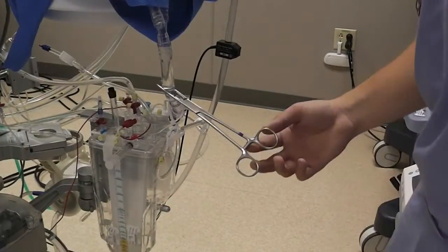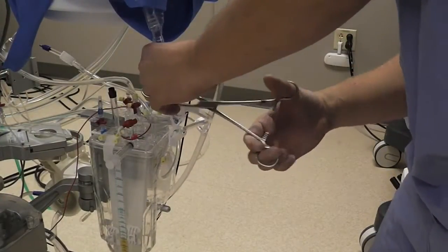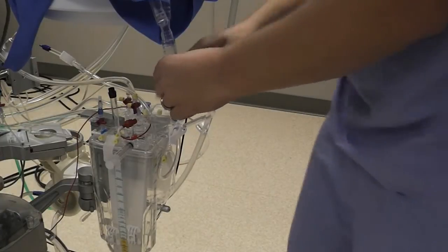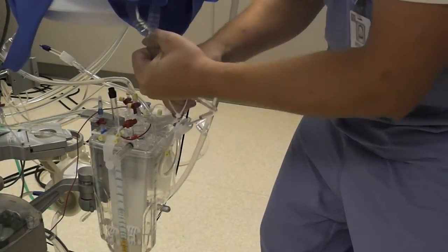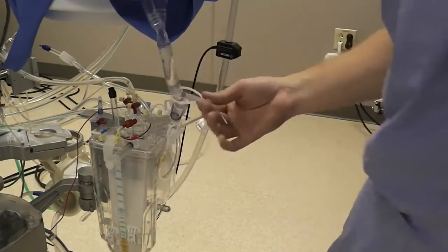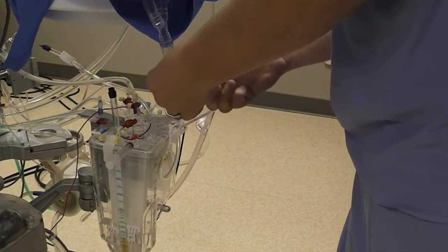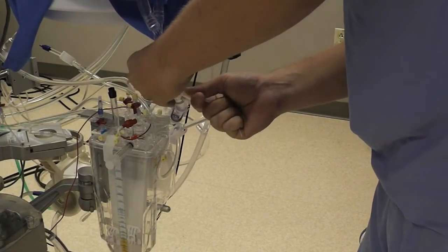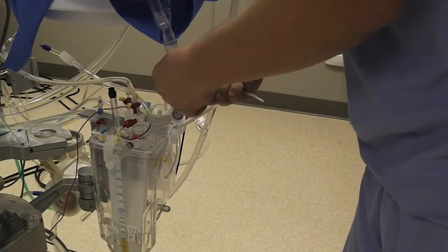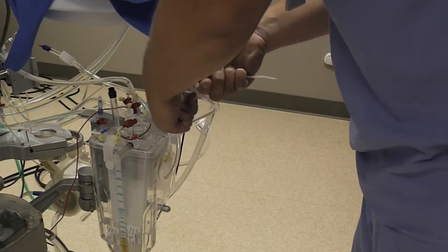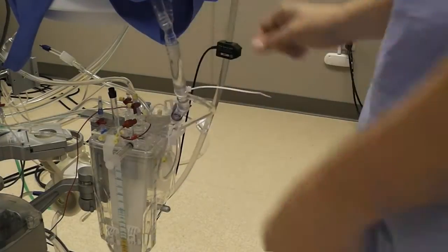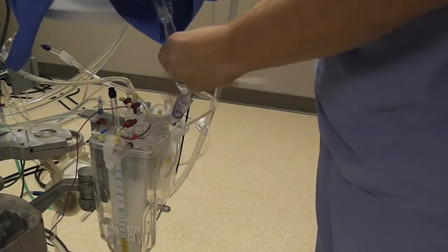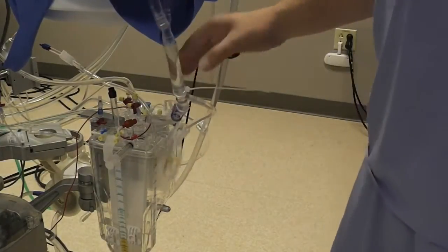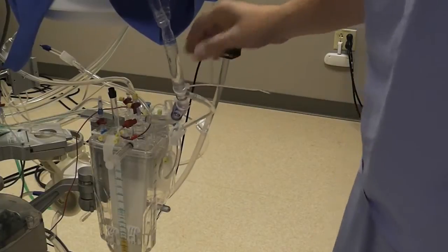Okay, after you've disposed of that, you're going to come back, carefully remove this clamp, and fully seat this connection all the way on, and this is where that zip tie comes in handy. That is kind of a wet connection, so I like to put a zip tie on here. It's not necessary, but it'll give you a bit of peace of mind. It's pretty low pressure, it's the venous side, but you know, and then just remove any air from that.